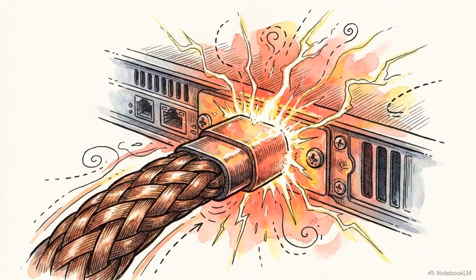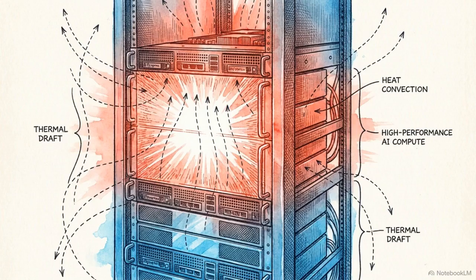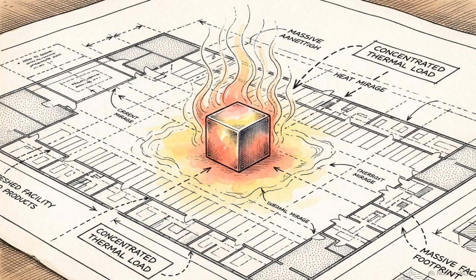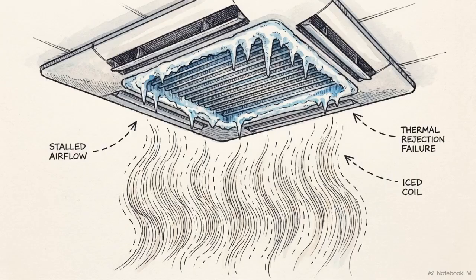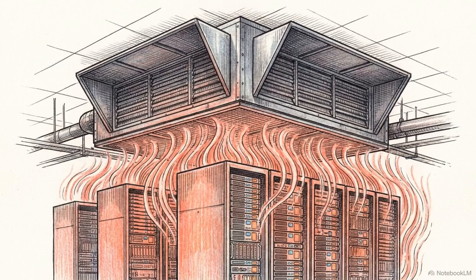Power consumption creates a secondary, unavoidable law of physics. Every watt of electricity that enters the compute load must be actively extracted as heat. Modern AI clusters concentrate immense power into extremely small footprints. This density completely overwhelms traditional air-cooled HVAC systems, which simply cannot push enough chilled air to offset the thermal load.